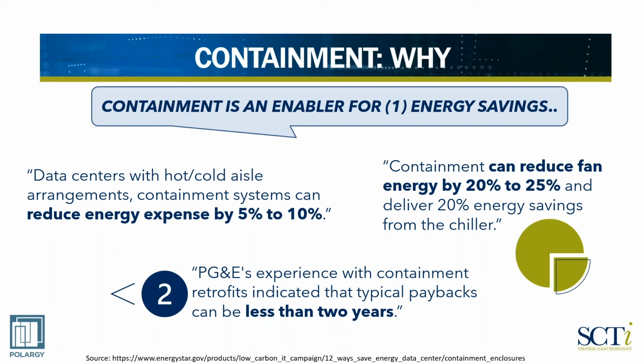If your system is using CRAC units or DX-based units, again, increase in temperature set points, controls on humidity, especially if you're going to cold aisle containment, and the concept of networking and sequencing to reduce the number of operating units. So when we go into a site, if we are doing containment, it's not just doing containment, it's doing everything else related to making that site operate better from a cooling point of view.